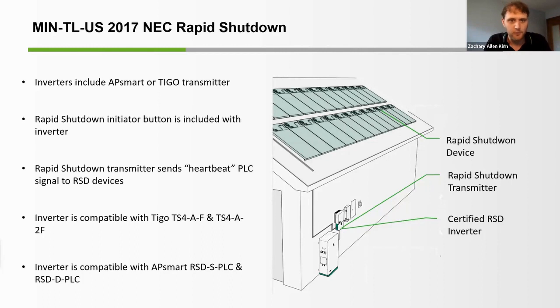So the inverter is compatible with the Tigo TS4-AF or the A2F, so either the single module or the dual module optimizer. The inverter is also compatible with the AP Smart RSD-S PLC and the RSD-D PLC, so either the single module or the dual module rapid shutdown device. Really trying to get as many devices ready to go with this inverter as possible, to make sure that this is a complete solution for your customers.